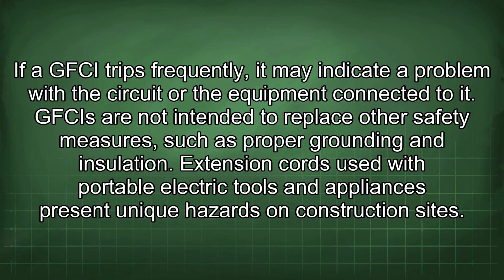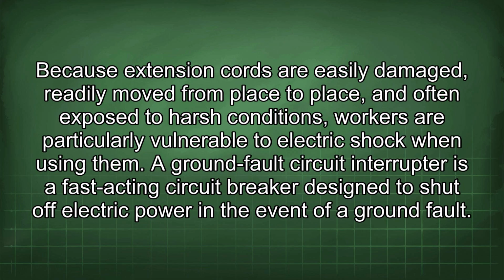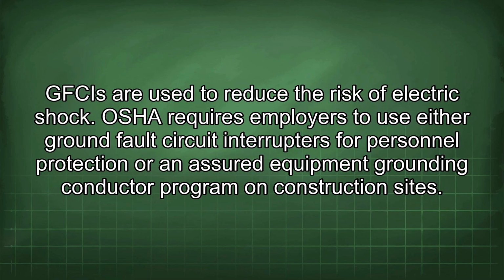Extension cords used with portable electric tools and appliances present unique hazards on construction sites. Because extension cords are easily damaged, readily moved from place to place, and often exposed to harsh conditions, workers are particularly vulnerable to electric shock when using them. A ground fault circuit interrupter is a fast-acting circuit breaker designed to shut off electric power in the event of a ground fault. GFCIs are used to reduce the risk of electric shock.